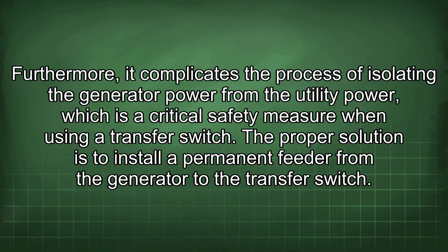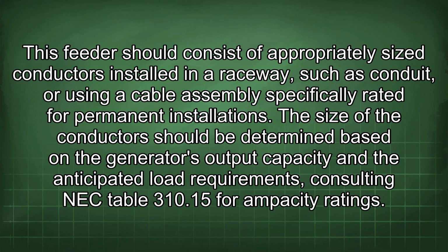The proper solution is to install a permanent feeder from the generator to the transfer switch. This feeder should consist of appropriately sized conductors installed in a raceway, such as conduit, or using a cable assembly specifically rated for permanent installations. The size of the conductors should be determined based on the generator's output capacity and the anticipated load requirements, consulting NEC Table 310.15 for ampacity ratings.